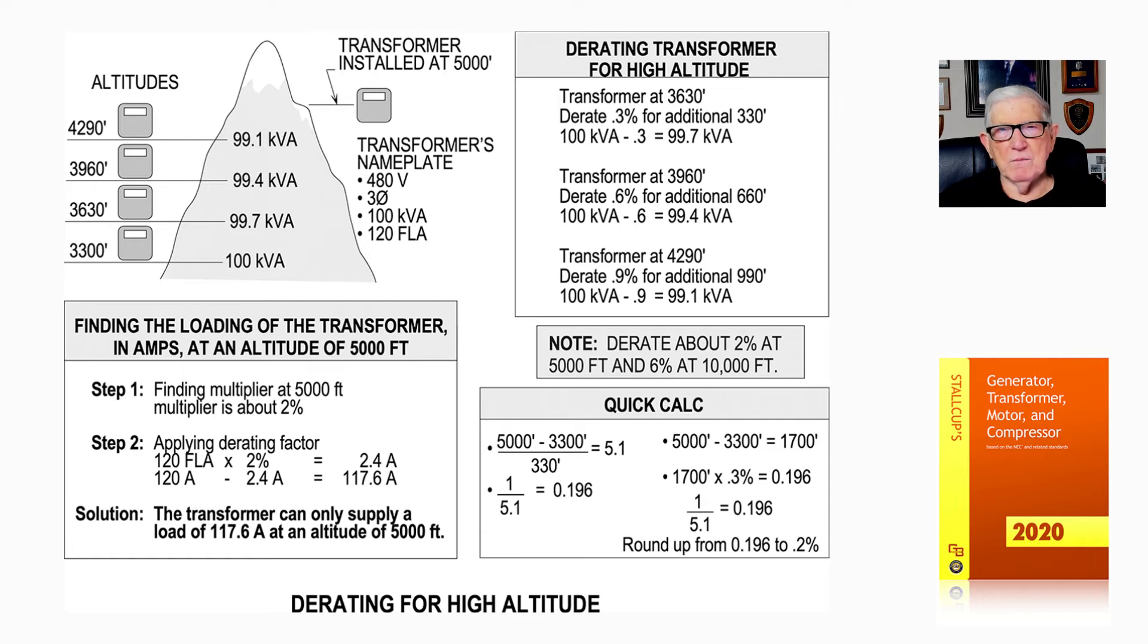Once you get above 3,300 feet above sea level, you have to derate the transformer. But notice it's not the same reduction in amps that you'd have for a motor as we'll see later. Transformers you don't have to derate as much.